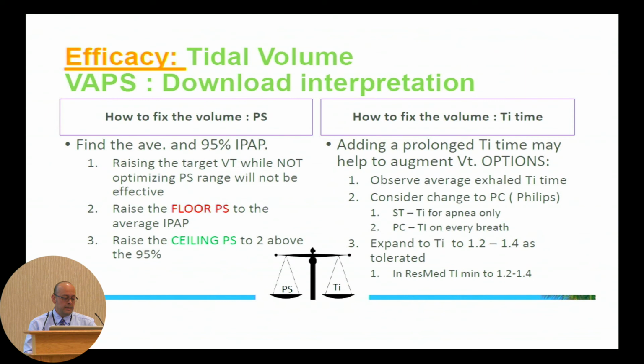And the 95th percentile is going to be your ceiling. And that's going to give you very likely elevated PS or IPAP pressures, but that's what you need to get to your target tidal volume. Is that not enough? The next thing that we discuss is increasing your inspiratory time. You can expand your inspiratory time to 1.2 seconds.